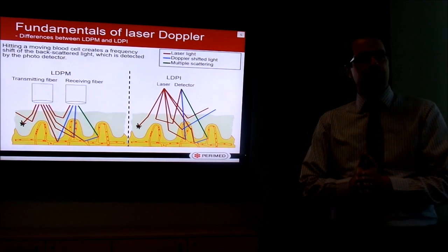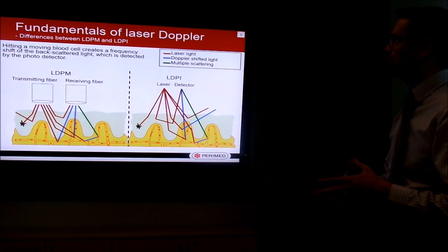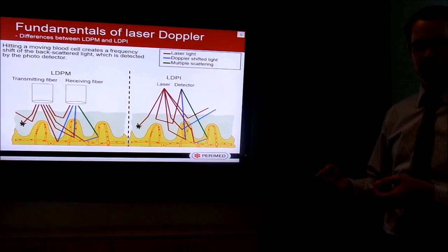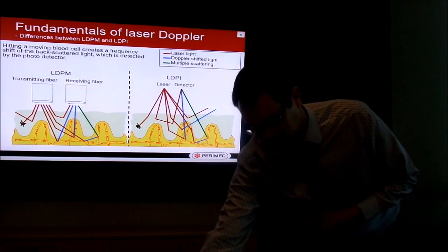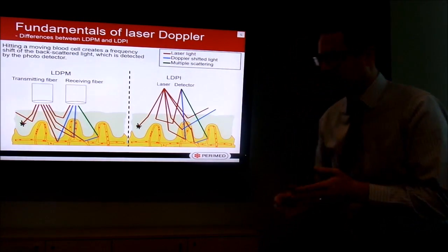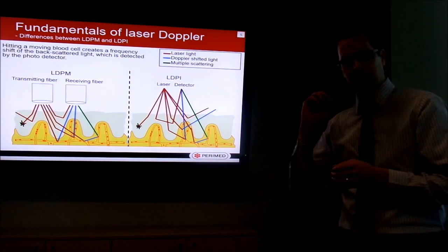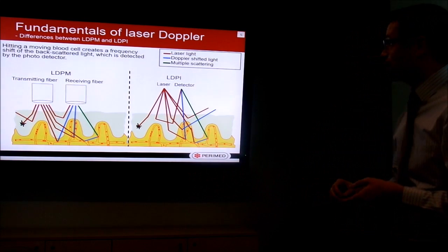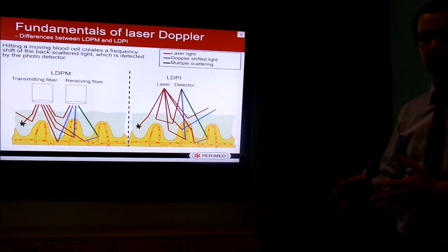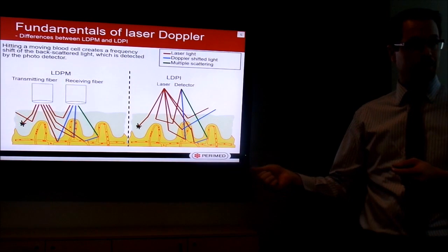Laser Doppler, how we're actually measuring this blood perfusion and changes in blood perfusion is we're sending laser light into the tissue in question. This is done with a fiber optic probe, such as this one right here. The probe has a transmitting fiber, so the laser source within the instrument is then being transmitted fiber optically to the tissue. The laser light will scatter in the tissue.